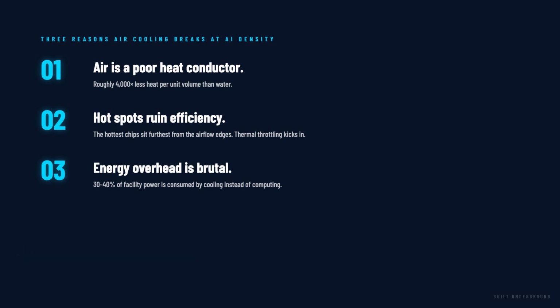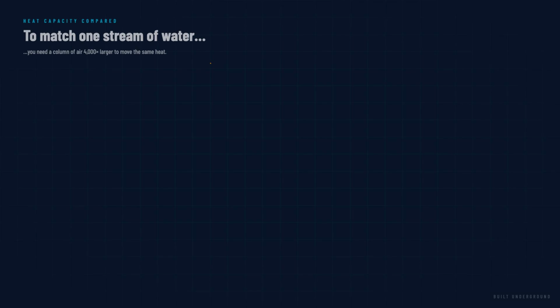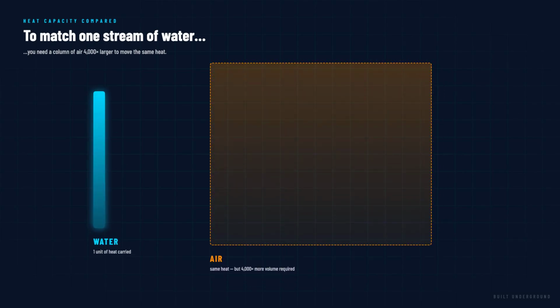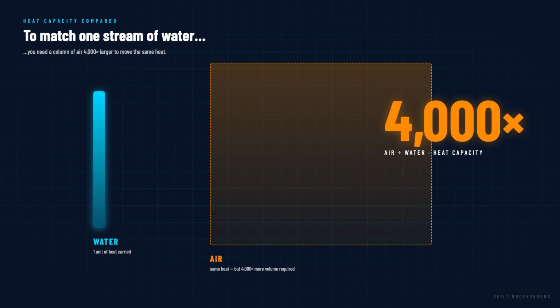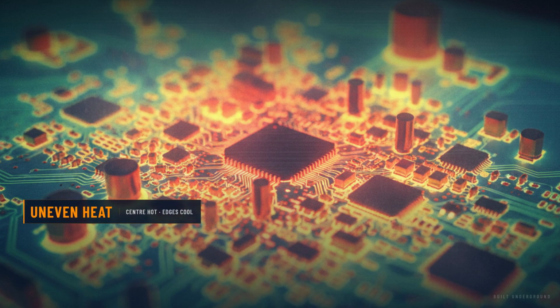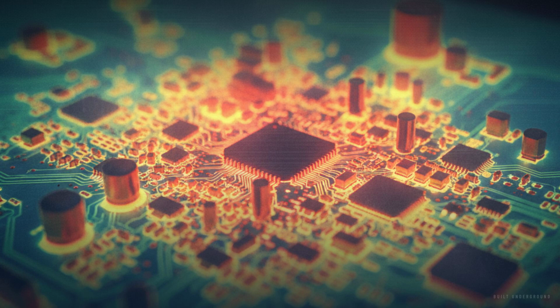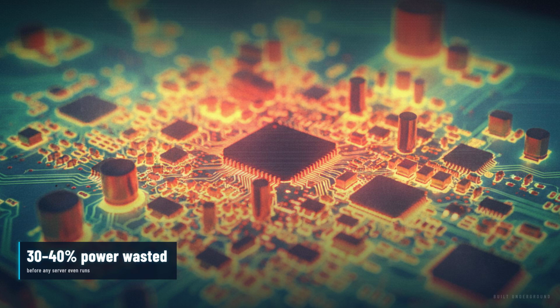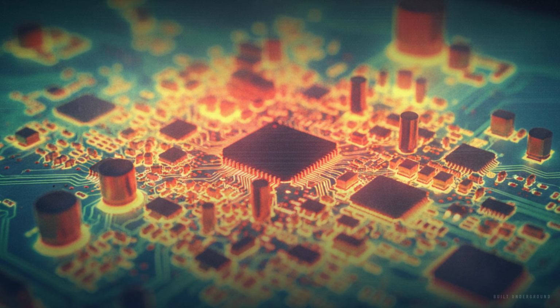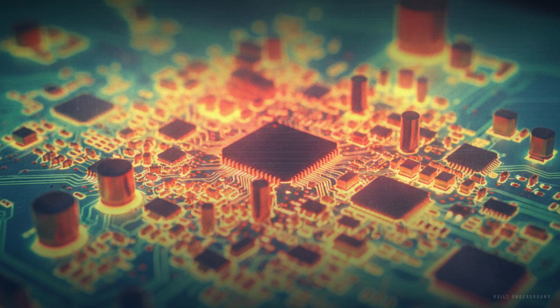To cool a high density rack with air, you need enormous volumes of it moving at high velocity, which means bigger fans, bigger ducts, bigger plant rooms, and more energy. Two, hotspots. Air does not cool evenly. The chips generating the most heat often sit in the middle of the server board, furthest from the airflow edges. Thermal throttling, where chips slow themselves down to avoid overheating, is a real performance limiter in air-cooled high-density environments. Three, energy overhead. In a traditional air-cooled data center, cooling can consume 30 to 40% of total facility power. That is power that could be running servers instead of running fans and compressors.